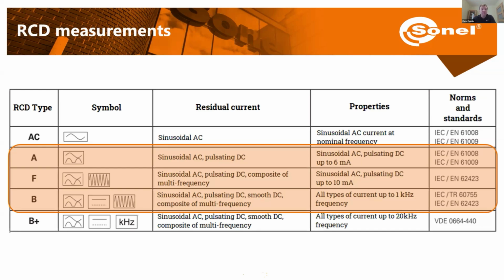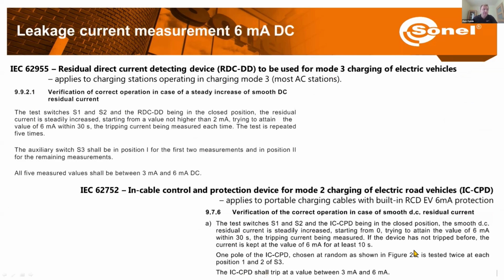And here, type B will trip whenever we have sinusoidal AC currents, pulsating DC, smooth DC, or a composite of multi-frequency. So whatever leakage current we are going to have, the RCD is going to trip in case of a fault situation. Then RCD type F is going to trip for sinusoidal AC currents, pulsating DC, or composite of multi-frequency up to 10 milliamps. And type A will work for sinusoidal AC and pulsating DC up to 6 milliamps. So that's why we see that for type A and F, we need additional protection.